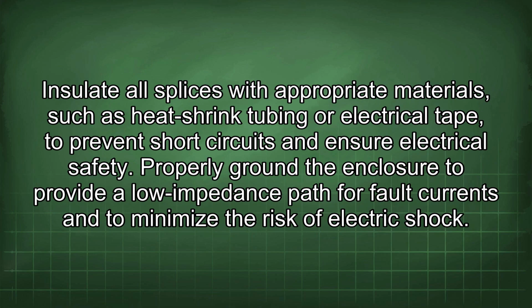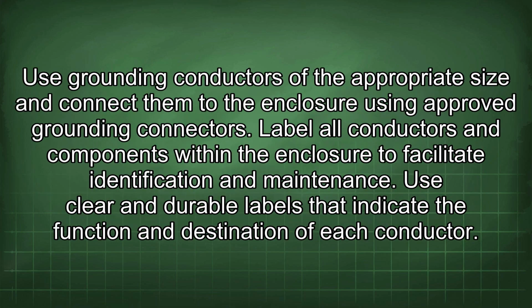Insulate all splices with appropriate materials such as heat-shrink tubing or electrical tape to prevent short circuits and ensure electrical safety. Properly ground the enclosure to provide a low impedance path for fault currents and to minimize the risk of electric shock. Use grounding conductors of the appropriate size and connect them to the enclosure using approved grounding connectors. Label all conductors and components within the enclosure to facilitate identification and maintenance.